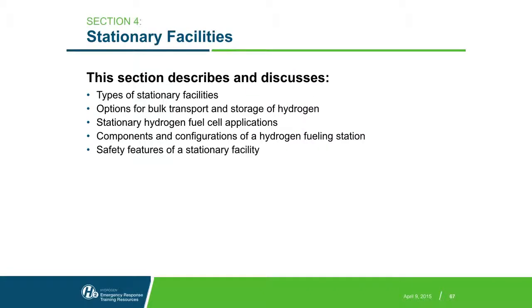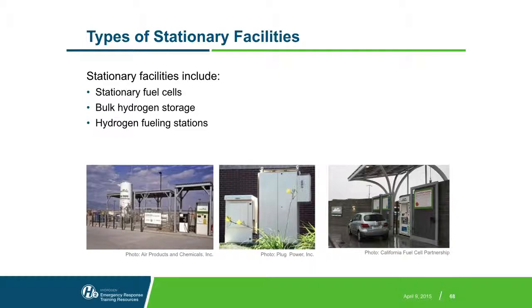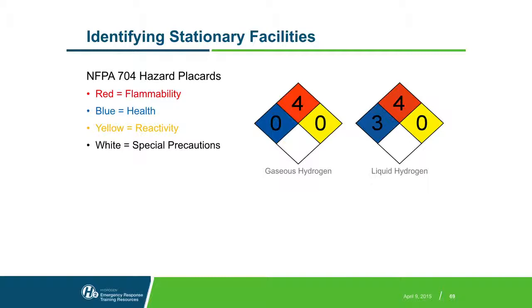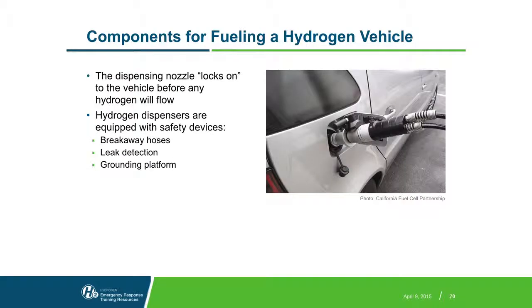So quickly, let's talk about fueling, and then we'll go outside and see the flame prop. There is the NFPA 704 diamond on here, but this is not being considered a stationary facility. The hydrogen fueling station would be. Stationary can be bulk storage, fueling stations, or stationary fuel cells. This diamond will be on one side of the container, and we'll see an image of that later. In terms of the fueling, they're following some of the same protocols and procedures as for vehicle fueling, in terms of the type of nozzle and the type of receptacle on the unit. That would be at 5,000 psi, a nozzle just like this.